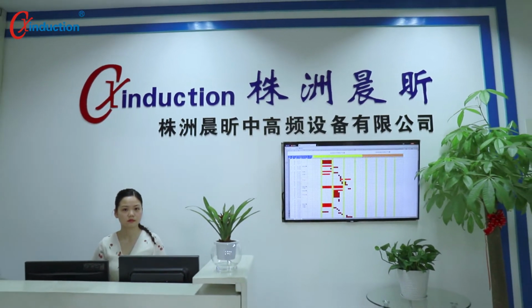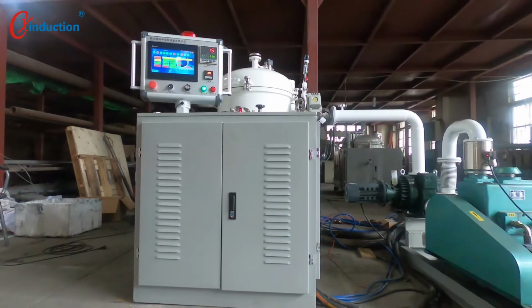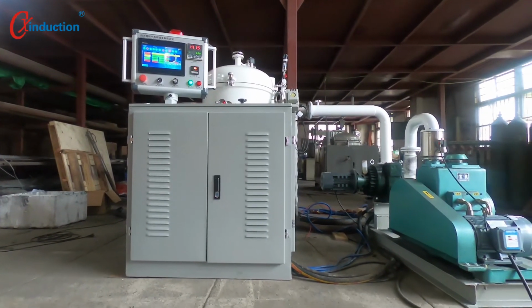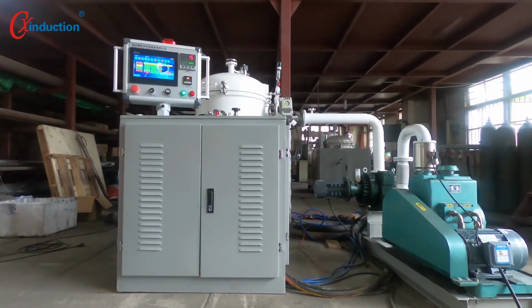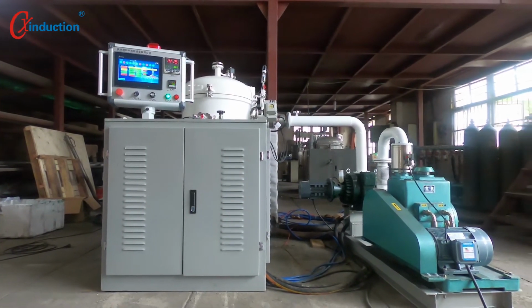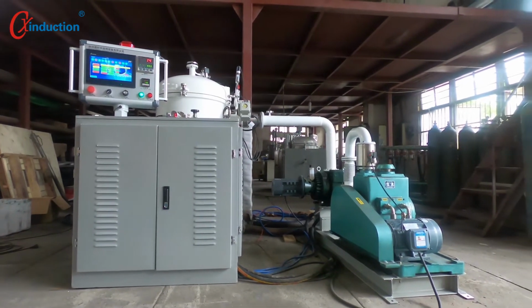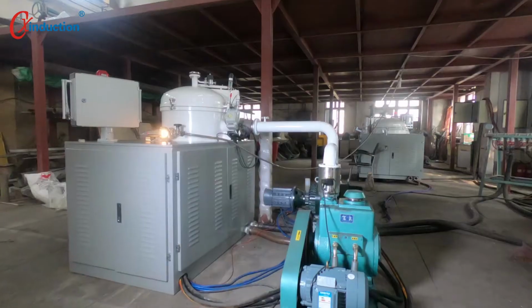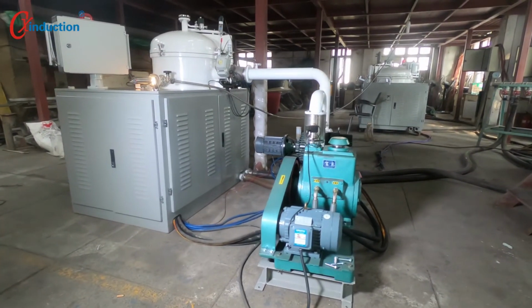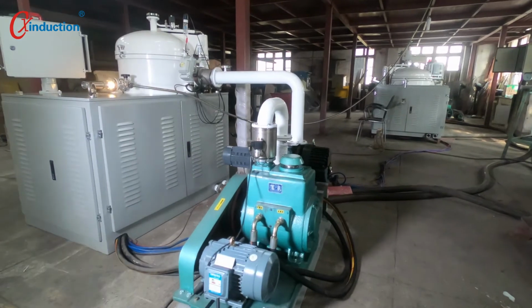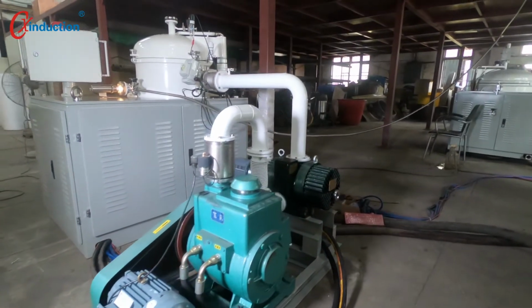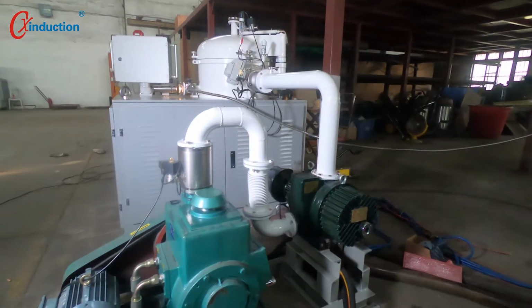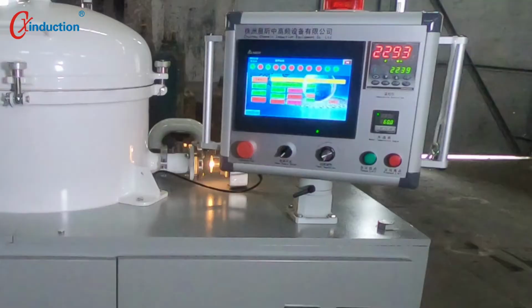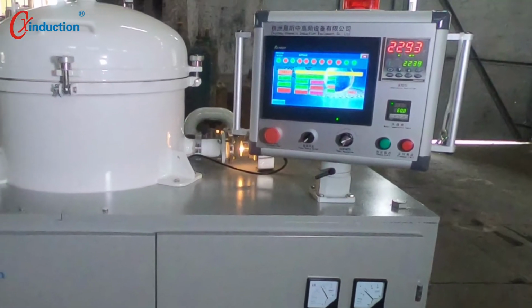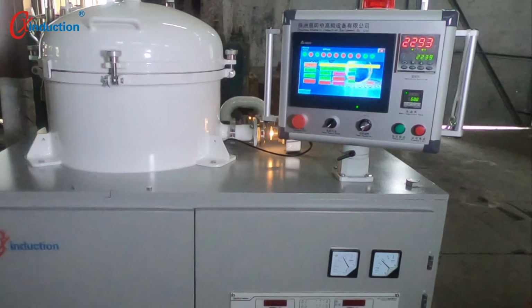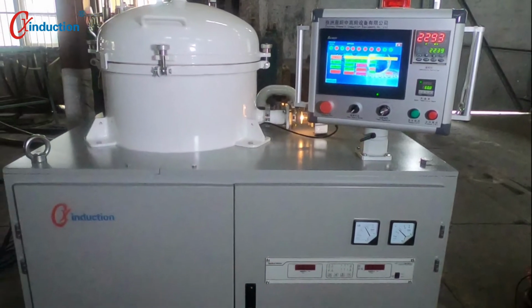Today, let's introduce you to a laboratory carbonization furnace. The laboratory carbonization furnace is of compact design, small in floor area, neat and beautiful. It is a resistance heating furnace that uses graphite elements. It can heat treat various materials under protective gas like inert gas or vacuum. The maximum working temperature is 2300 Celsius, which can meet all conditions of the carbonization process for various carbon materials.